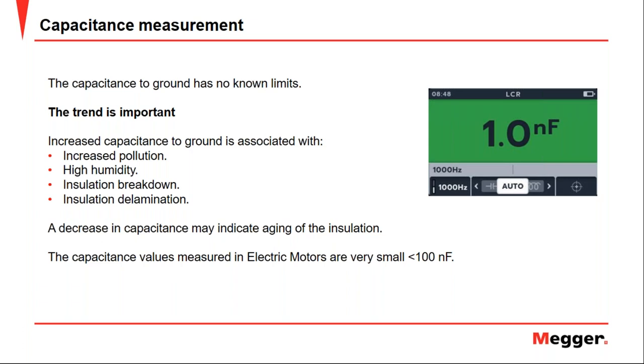Again, the important thing here is, as we know, electric motors have a big inductive effect. Therefore, their capacitive effect is very small. So the equipment used to measure capacitance must be able to read very low values, because in motors, capacitance is generally less than 100 nanofarads. These two variables, the inductance and the capacitance, are always useful if we build a trend. With the trend, we can make decisions. Only one measurement doesn't tell me anything about my insulation system.